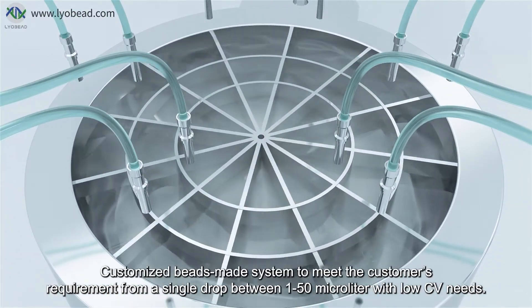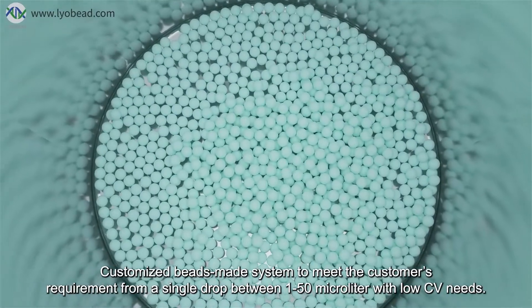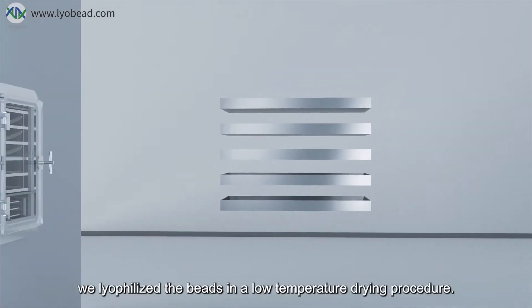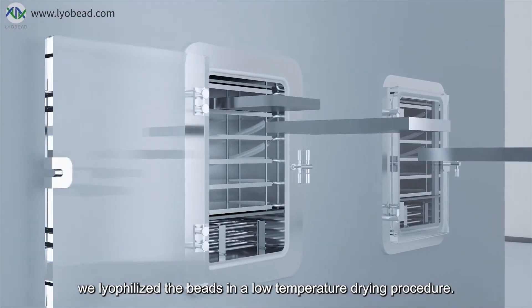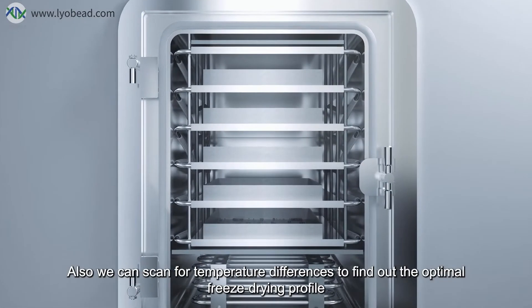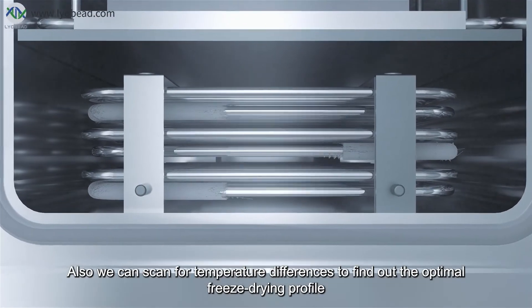A customized bead-making system meets customer requirements, producing a single drop between 1 to 50 microliters with low CV needs. After pre-freezing, we lyophilize the beads in a low-temperature drying procedure. We can also scan for temperature differences to find the optimal freeze-drying profile.